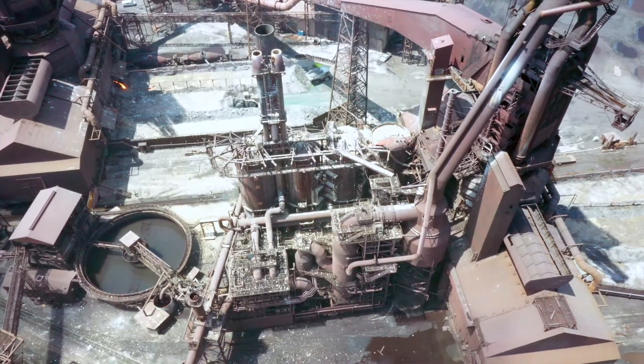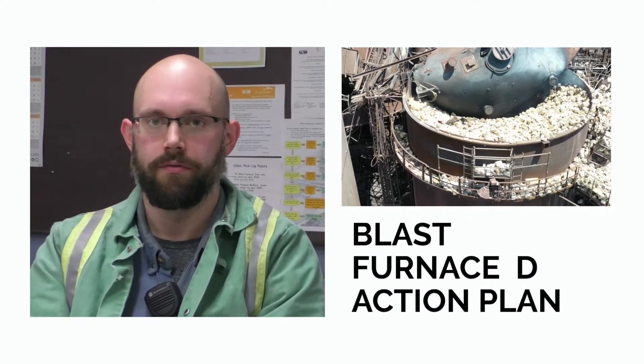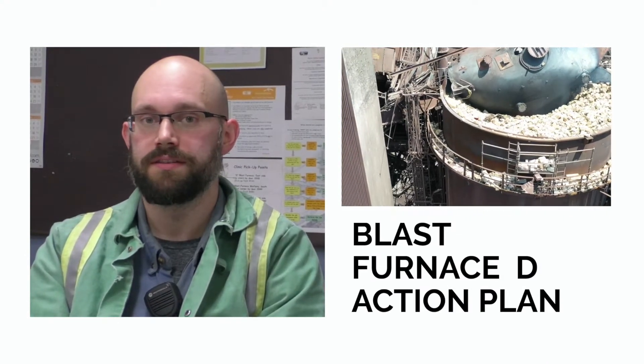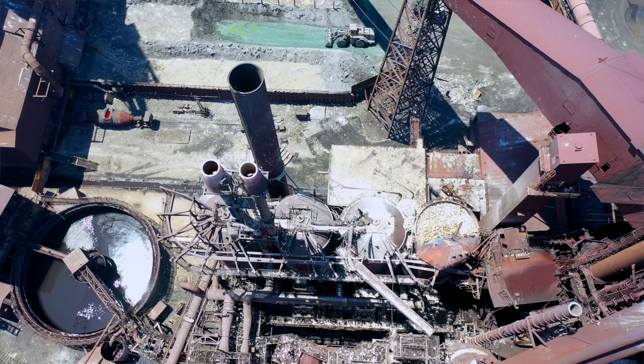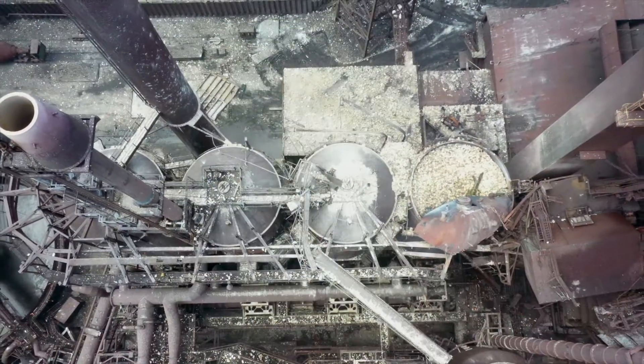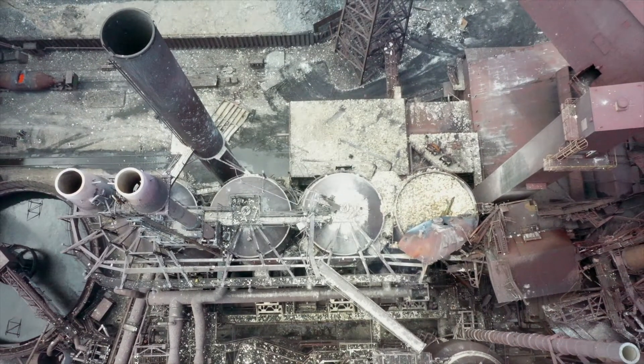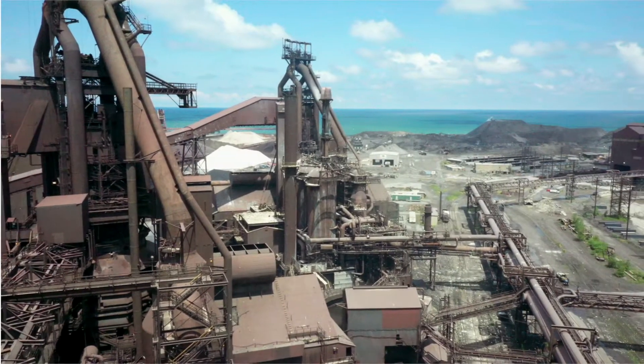The Burns Harbor team started creating an action plan — a pretty intense plan. They ended up putting in about 10 remote PLC racks all over the furnace, ran 75,000 feet of cable, made about 35,000 to 40,000 electrical terminations, and touched roughly 250 to 300 devices out in the field. They put two temporary hydraulic units on top of the furnace — one to run the IHI top and one to run the bleeders — and another diesel unit to run the snort valve.